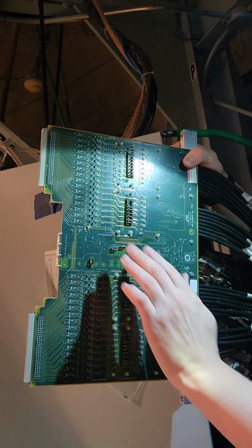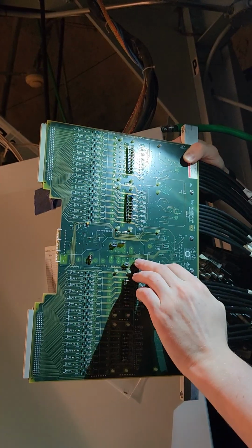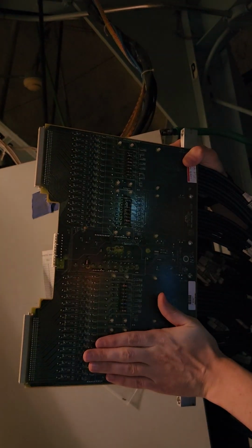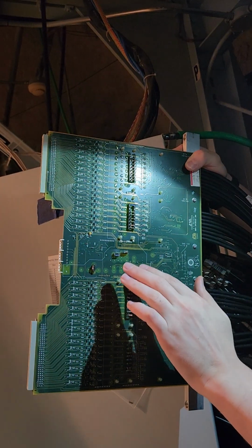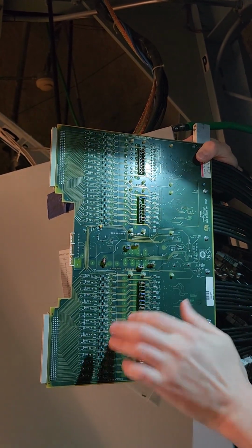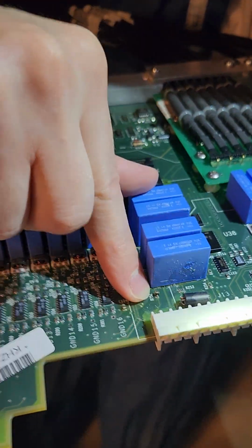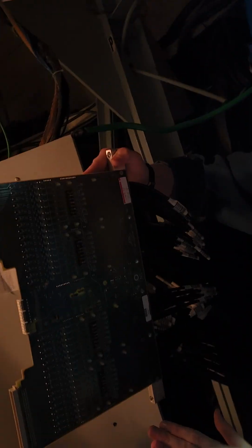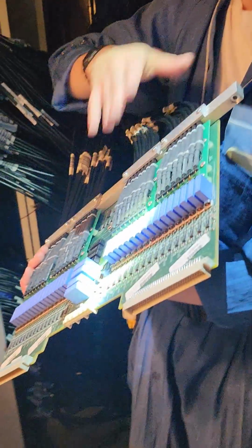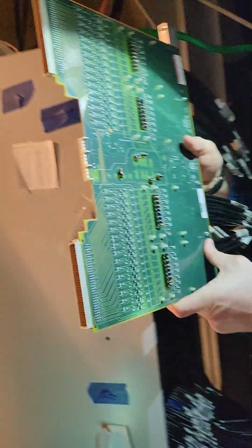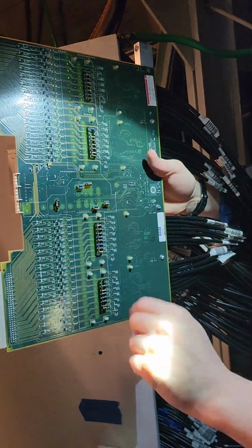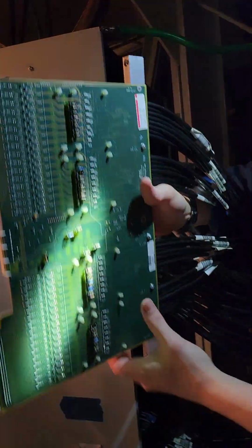If that happens, and suddenly this resistor is no more, when we're running, it'll look like, oh, we just lost all of these, right? If we haven't dissipated that breakdown current enough, the next thing it's going to go through is one resistor right there, this R252. It will then take that one out, and if that's the case, it then looks like we've lost all of this. That's fine. We just tell our control software, okay, we're going to ramp this down, we'll open up these relays, we'll make a note of it, we'll fix it when we can. It happens. So when you pull it out, you'll see, oh, yeah, that resistor went bad, so that PMT is bad. We pull that, replace the feed, all good.